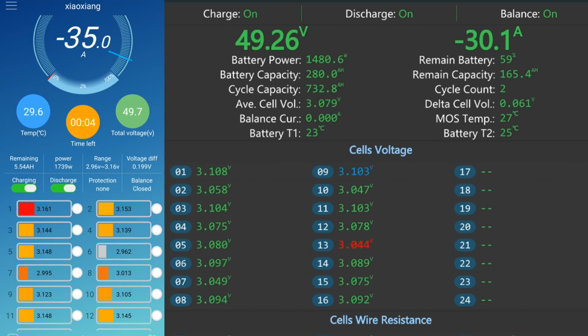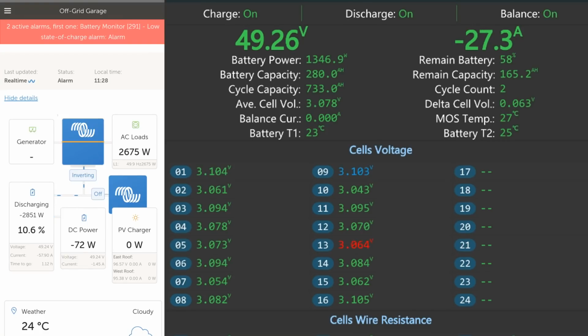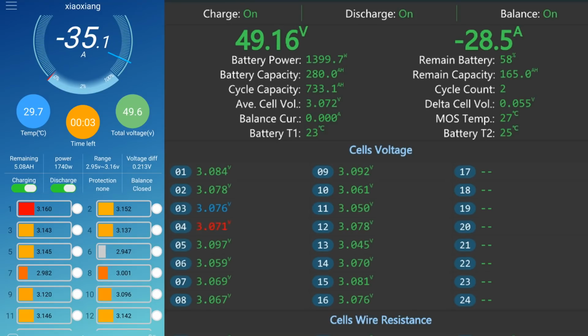I need to pee. Yeah, we will turn off the batteries at 2.55 volts if one of the cells hits 2.55, which is potentially cell number 6, because in the JK battery there's not much going on. We've got only 60 millivolt deviation at this super low state of charge. Battery monitor claims we are at 10% state of charge now, all in total, which may not be true. No, I don't think it's true. It's too high. We are lower than that. Cell number 6 is still holding.